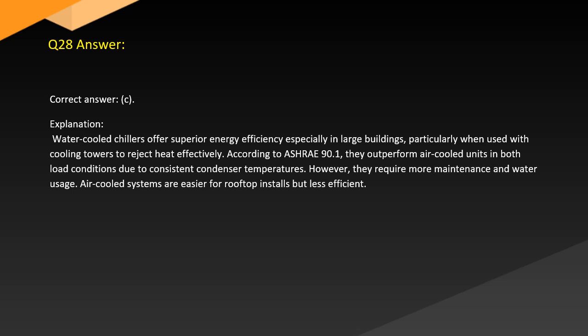Answer. Correct answer: C. Explanation. Water-cooled chillers offer superior energy efficiency, especially in large buildings, particularly when used with cooling towers to reject heat effectively. According to ASHRAE 90.1, they outperform air-cooled units in both load conditions due to consistent condenser temperatures. However, they require more maintenance and water usage. Air-cooled systems are easier for rooftop installs, but less efficient.